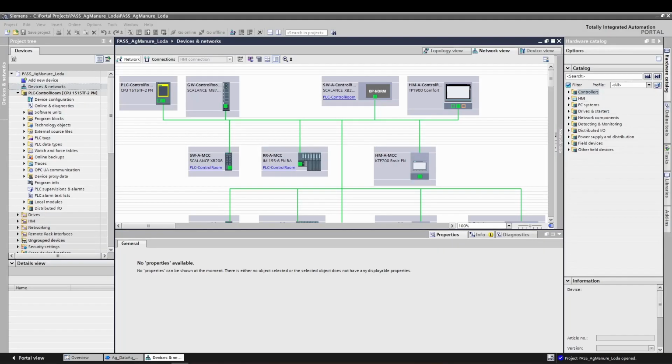What is a data record? A data record is a piece of communication that is available for an I/O device. Normally, when we think about I/O, we think about what's called cyclic communication. Cyclic communication happens ever so often, however, how often is determined by the actual PLC itself. In the Siemens world, that'll happen every scan, and all the I/O will get updated and made available to the PLC. Let's take a look really quick at what that looks like in the PLC.